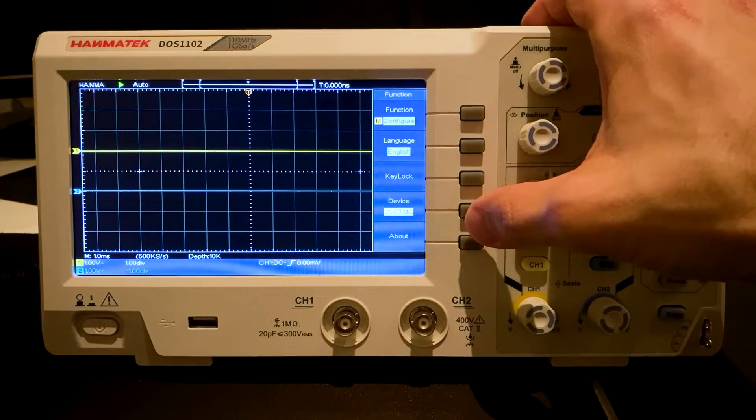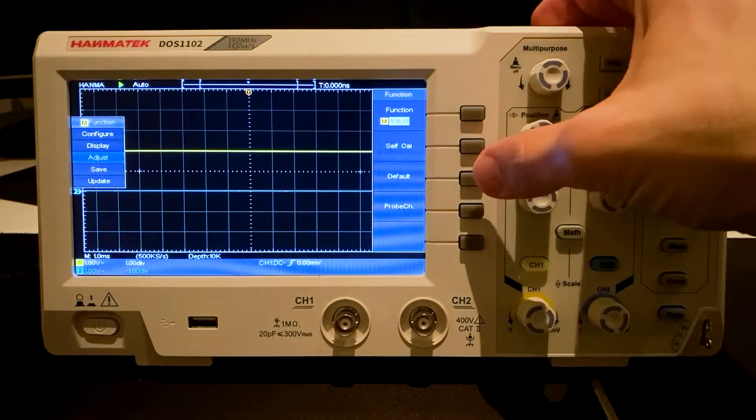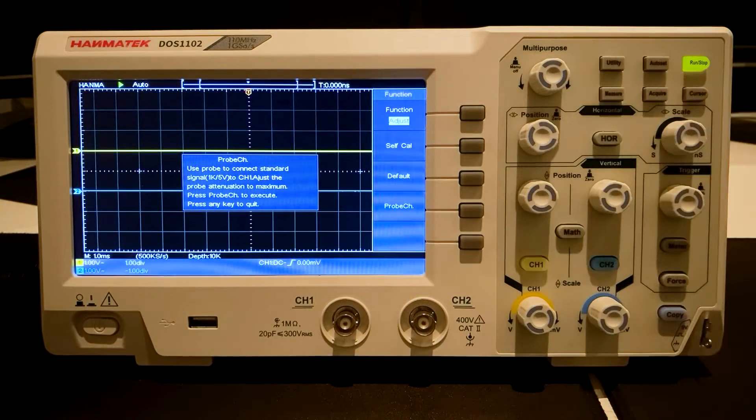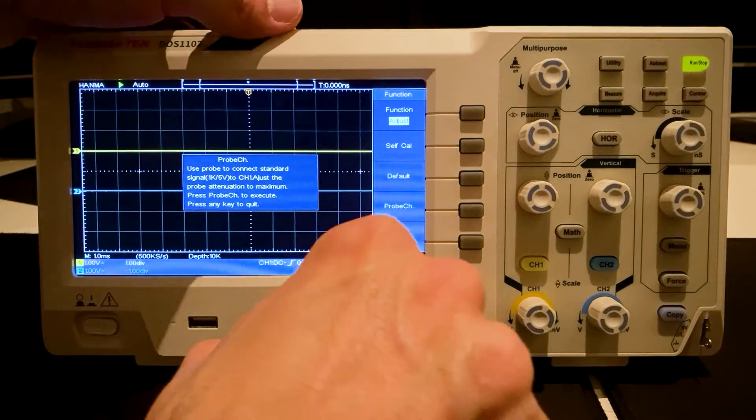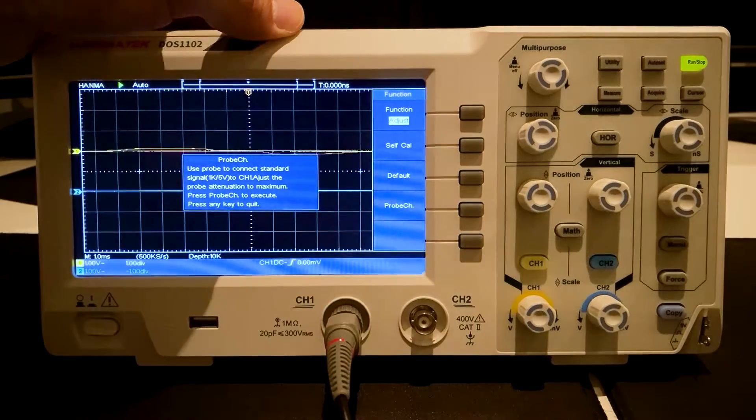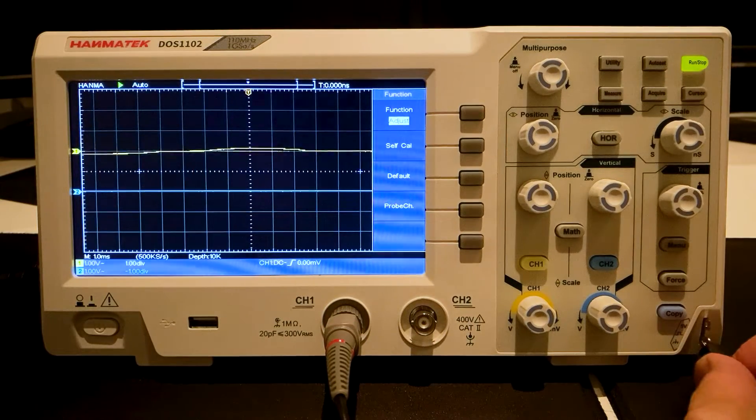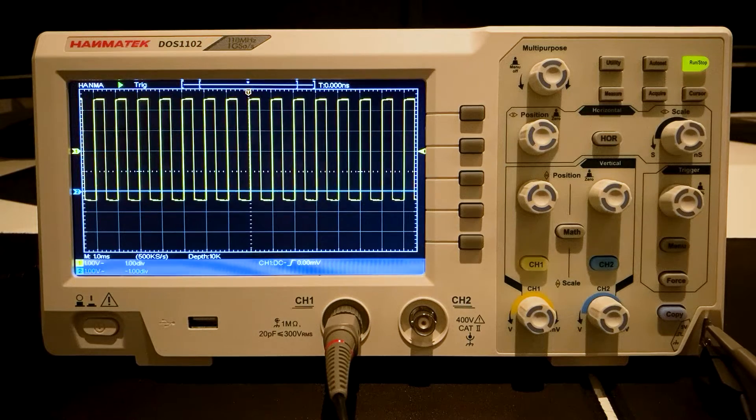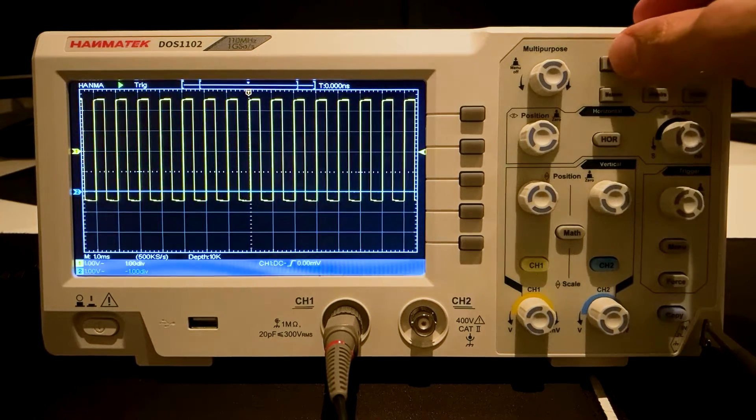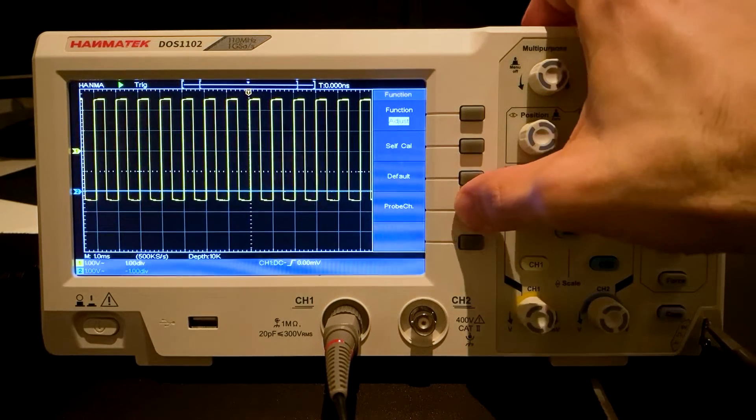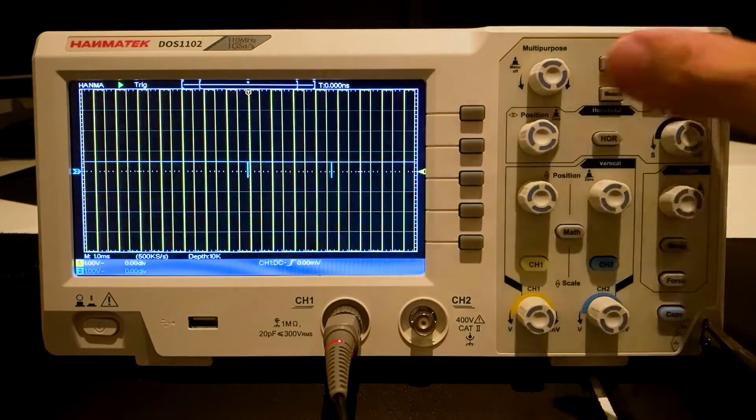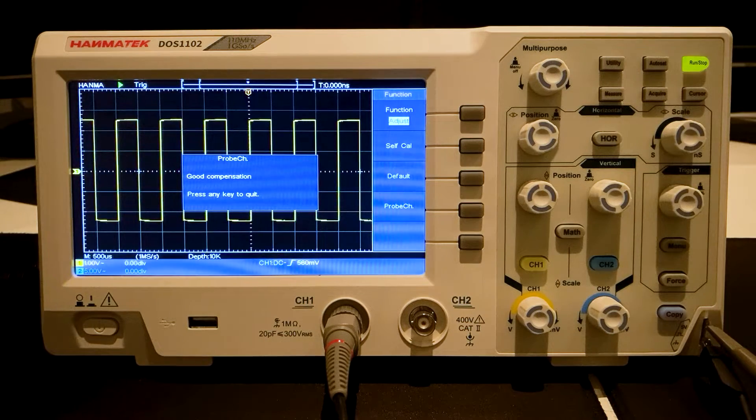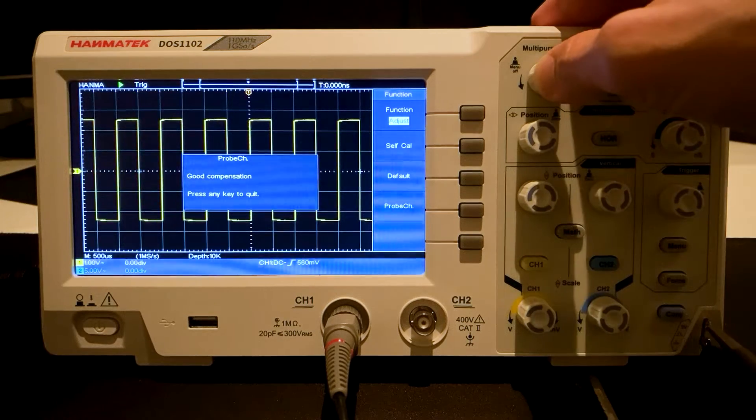The last option in adjust is probe check. Connect the probe to the BNC connector and press the probe channel button. The probe is measured and the result is good. We calibrated the probe well in the previous step.